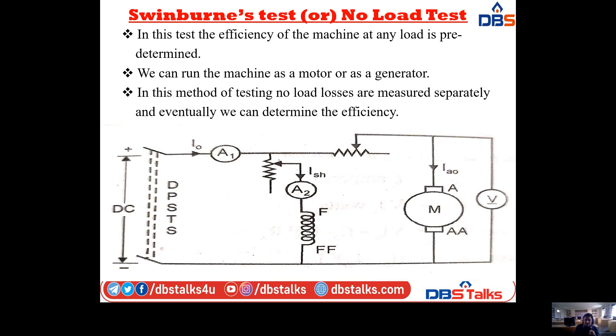The diagram for Swinburne's test uses a DC supply through a DPST switch. Ammeter A1 measures the no-load input current, and Ammeter A2 is connected to the field winding to measure the shunt field current. A voltmeter is connected across the motor to measure the supply voltage, and the no-load armature current is also recorded.